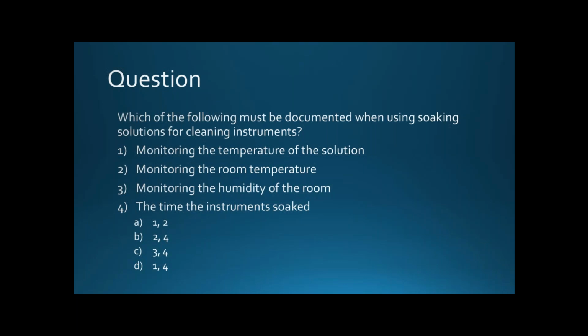Yep, you guys all got this one. It's D. So they need to make sure they're monitoring the temperature of the solution and the amount of time the instruments were soaked. And again, those two values are based off of what is in the IFU for that specific disinfectant.